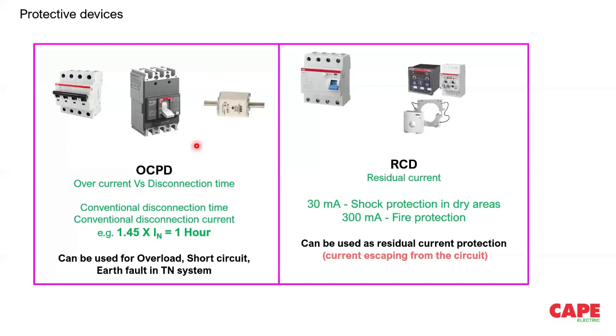So basically, RCD is a device. A 30 milliampere RCD is for shock protection in dry areas. Please note, dry areas is also very important, not for wet areas. And 300 milliampere is for fire protection. Leakages from equipment can ignite fire. An RCD of maximum 300 milliampere residual current can protect your installation from fire.